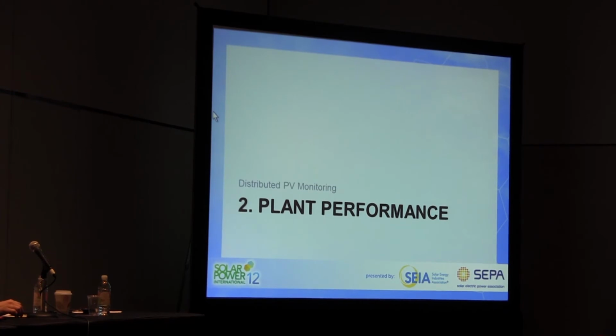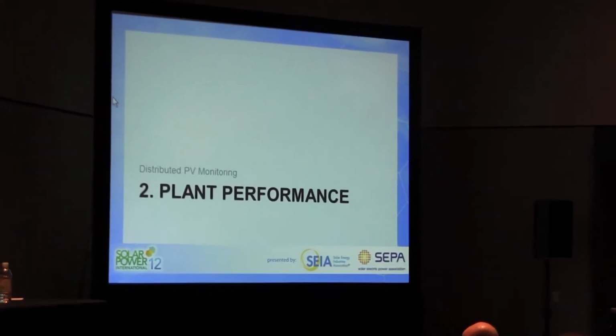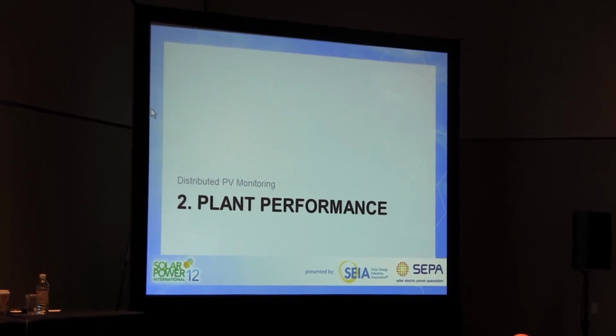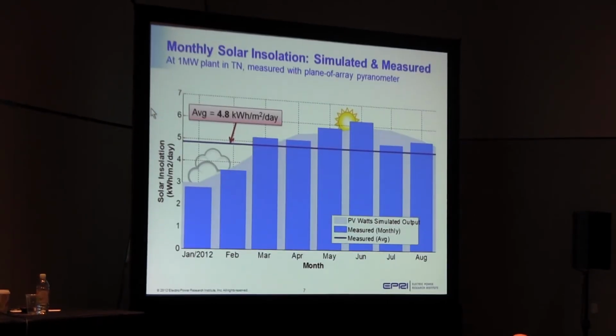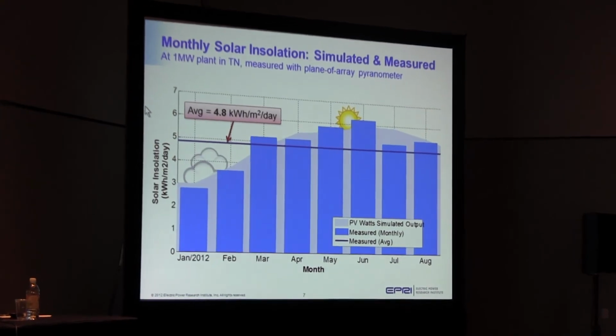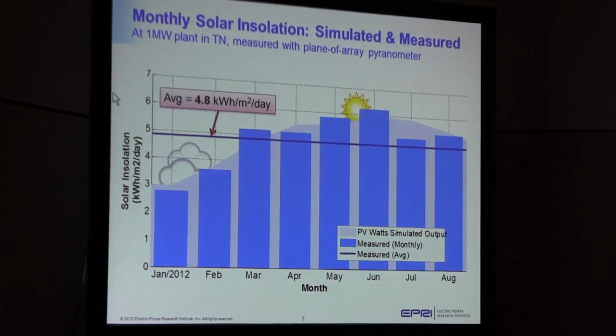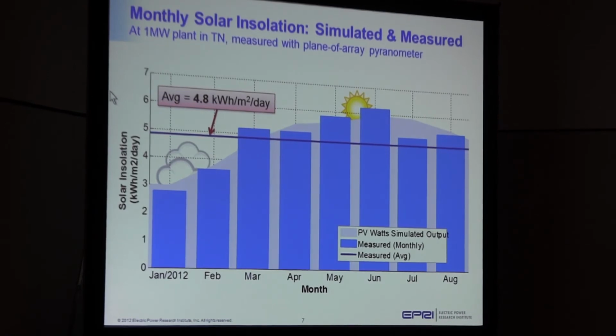So now I'll use this 1 megawatt site and let you see how this plant is performing since January of this year. So we'll look at about 8 months. We'll start off with solar insolation. So this is how much sunlight is hitting that site, and we're using a plane of array pyranometer. And you can see in January, it's pretty cloudy, as we would expect in Tennessee. As we roll over into the spring and early summer, we have a lot more daily insolation available. And you can see some degradation in July and August, and we suspect that's probably due to excessive amounts of clouds. So southeast, we love our clouds, and they're everywhere.